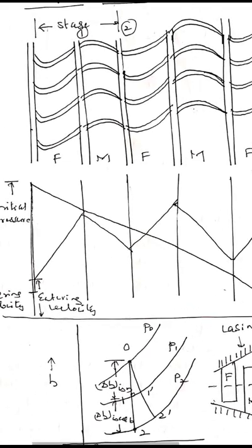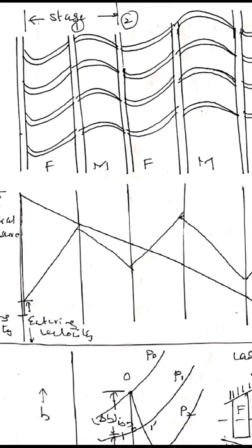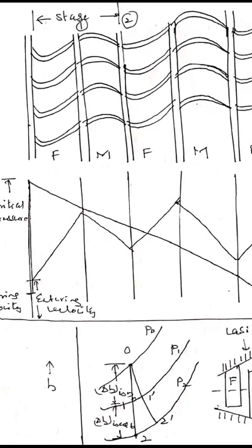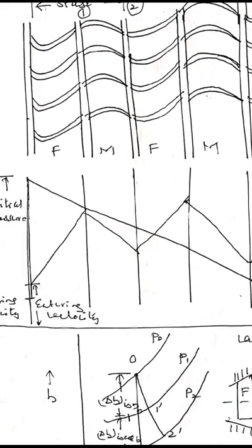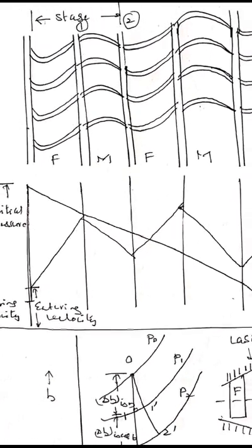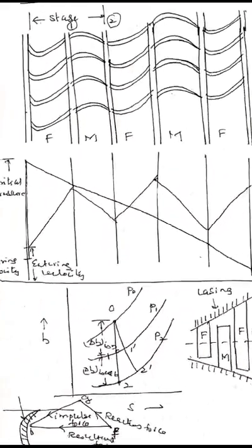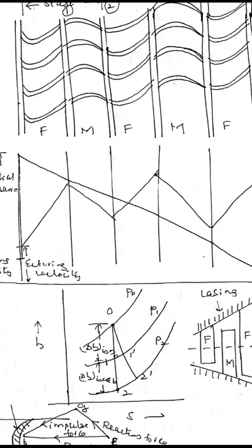The fixed blades will act as nozzles and they convert the pressure energy into kinetic energy. This kinetic energy generated is utilized on the moving blades. The high velocity jet of steam issuing from the fixed blades or nozzles will flow over the moving blades and will suffer a change in direction and hence momentum, giving rise to an impulse force which is proportional to the rate of change of momentum.